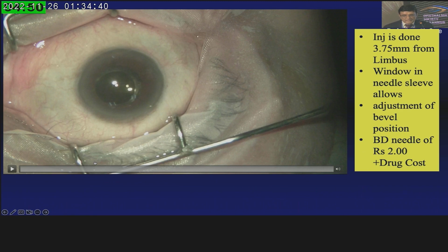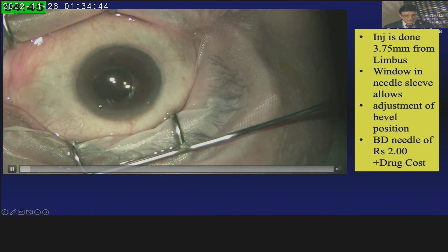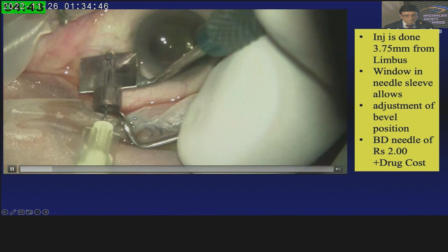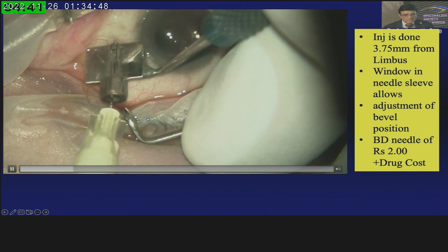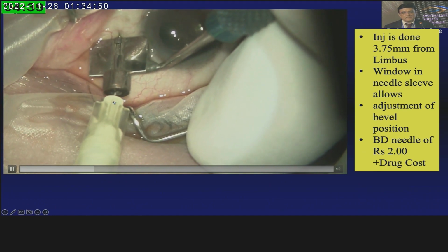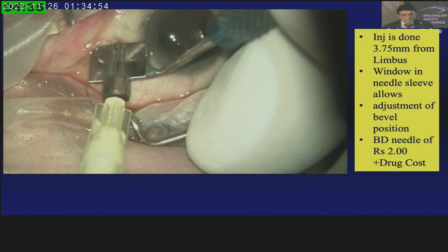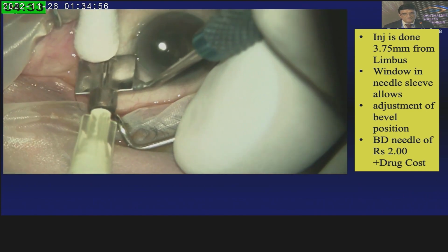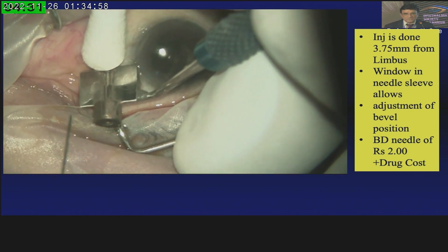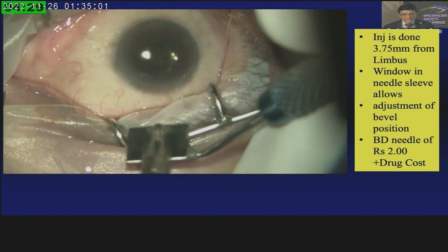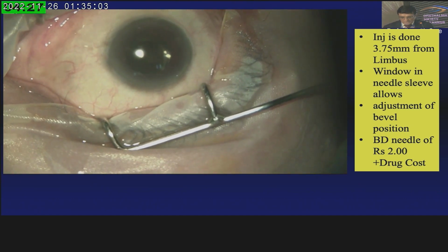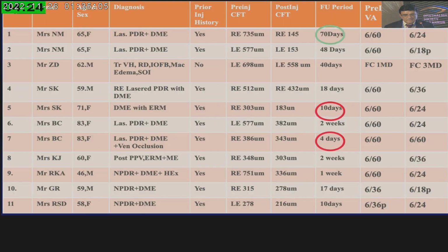the human studies, and you can see here that the device is being used when injecting into the eye. Normally I inject it in the inferotemporal or the inferonasal quadrant. We did OCT analysis of the scleral thickness and found out that these two quadrants are the best to choose, and we have nomograms for the device to choose based upon the thickness of the sclera.